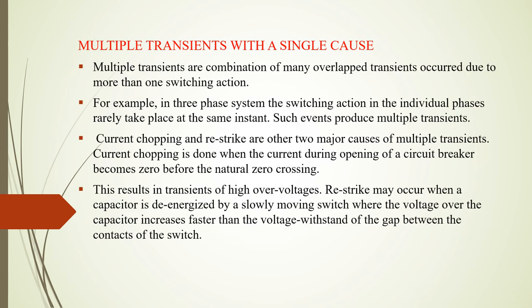Multiple transients, as the name suggests, are a combination of many overlapping transients occurring from more than one switching action. For example, in a three-phase transmission system, switching actions in individual phases rarely take place at the same instant, producing multiple transients. Current chopping and restriking are also major causes of multiple transients. Current chopping occurs when the current during the opening of a circuit breaker becomes zero before the natural zero crossing, resulting in high overvoltages. Restriking may also occur when a capacitor is de-energized and the voltage across the capacitor increases faster than the voltage withstand of the gap between the switch contacts.